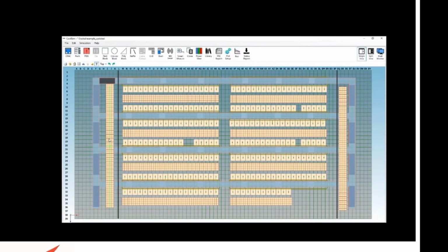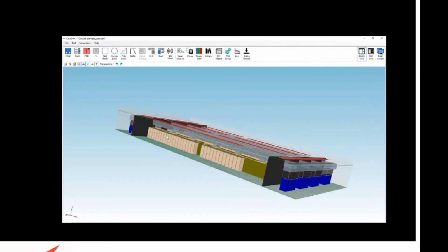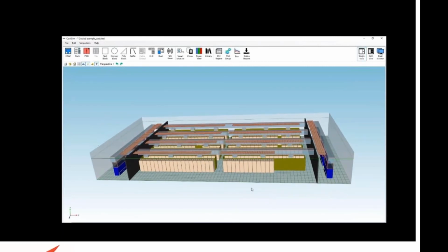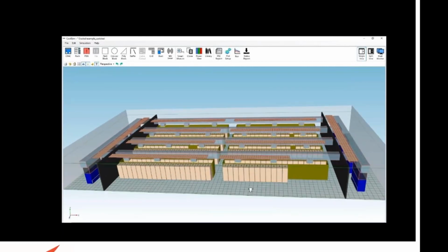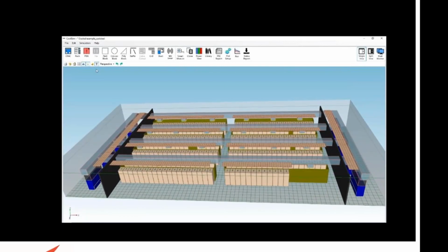If we shift this into 3D and take a look at it, that's a pretty good looking data center. Here again, I'm aligning my returns. But that's a nice design now. Now I'm dumping cold air into those cold aisles. I have eliminated the leakage back to the CRAC units and forced the hot air to go up into the roof.